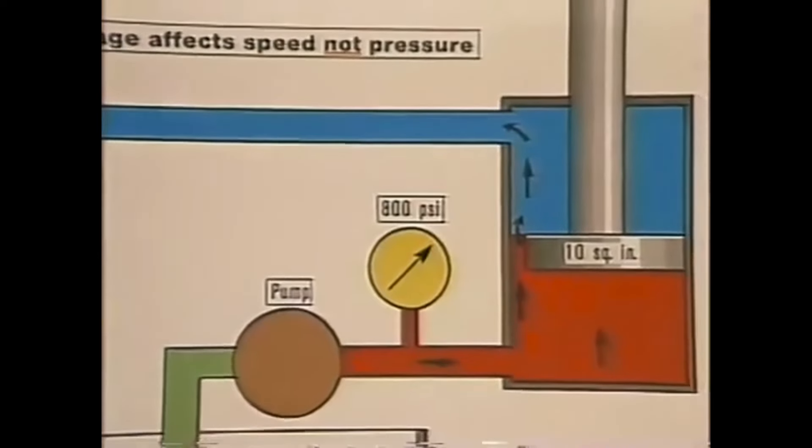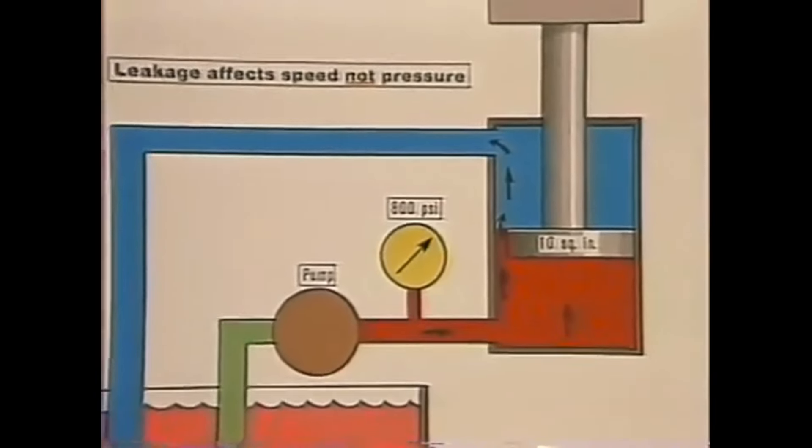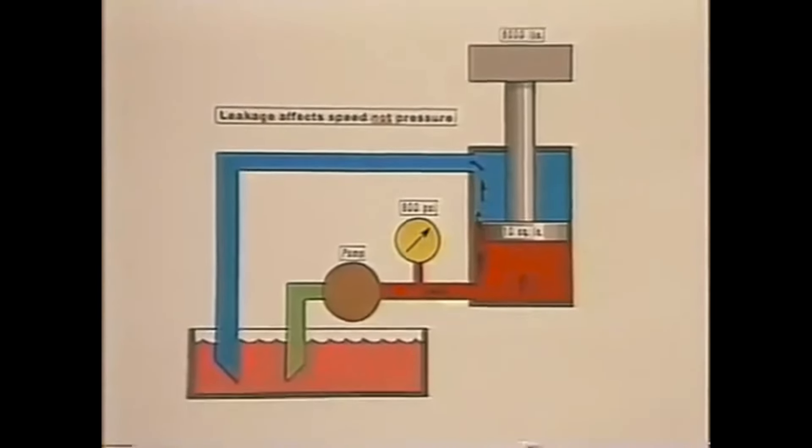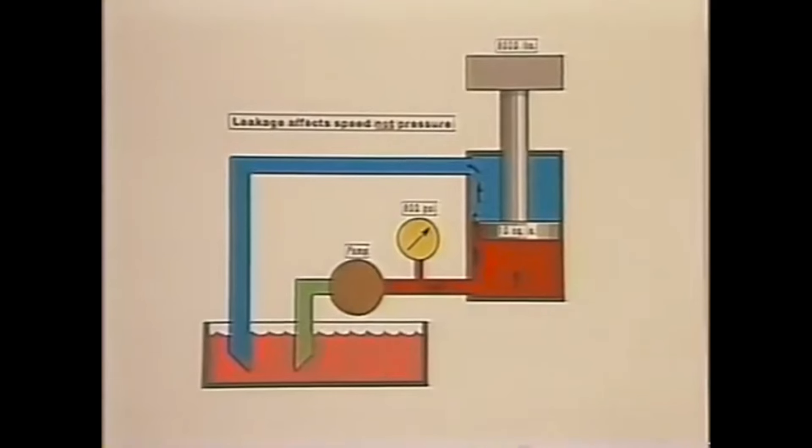If a cylinder stops or even slows down, either you're not putting as much oil into it as you were, or it's leaking past the piston. To check, block the cylinder so it can't move, and remove the opposite line. Be sure it's the opposite line, not the side under pressure, or you'll be sorry.